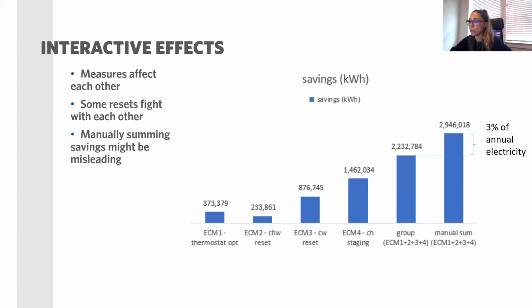This example shows an industrial facility which has very high electricity usage in a year. Each individual ECM is modeled, but when you just sum them versus when you group them, the delta is actually 700,000 kilowatt hours, which corresponds to 3% of the annual electricity of that building. So this could be misleading in terms of savings. In general, the resets could be fighting with each other, and there's no way you can capture that when you run them individually and sum them.